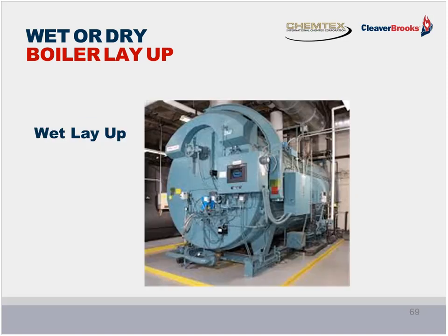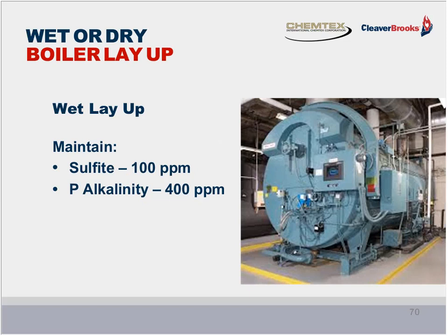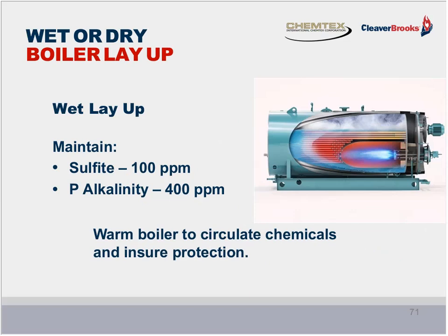You've got wet layup and there's dry layup. On the wet layup, what happens is you maintain the sulfite residual of about 100 ppm, and you want to have 400 ppm of p-alkalinity in the boiler. But what you also want to do is you need to warm that boiler up to circulate that water around to ensure that you have protection in the entire boiler, not just settling into the bottom where that oxygen scavenger has settled.